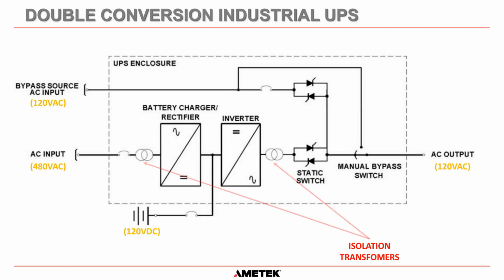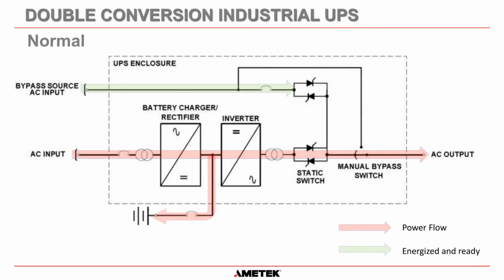What we're going to do is go over each of the blocks inside of this UPS one at a time as we go through the slides. But first of all, we're going to go over the power flow of a normal UPS in its different modes of operation. On the screen here, you'll see that we have red, and down in the bottom right-hand corner you can see the key. If you see red, there is power flowing, and if you see green, it is energized and ready, but there is no power flowing.